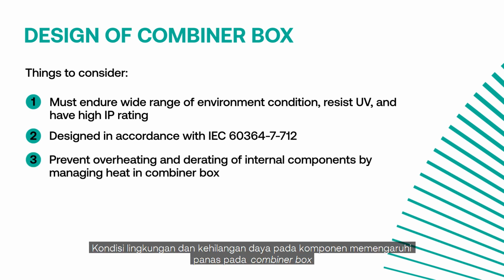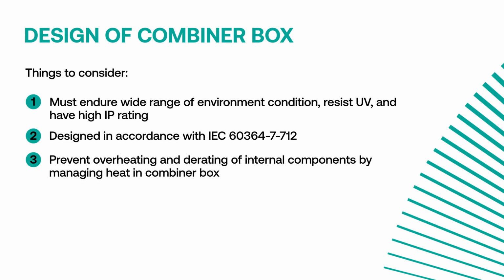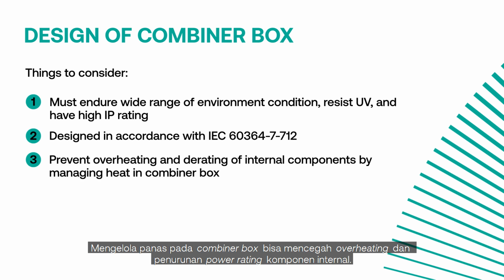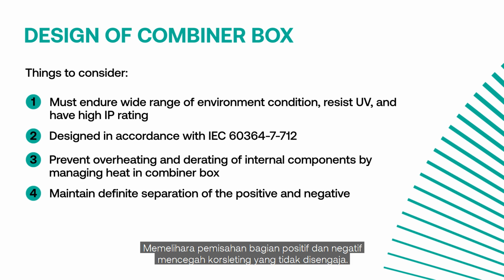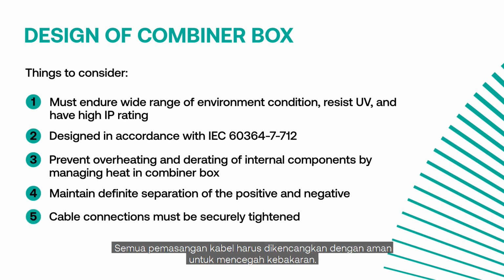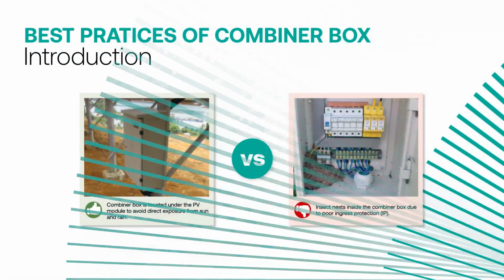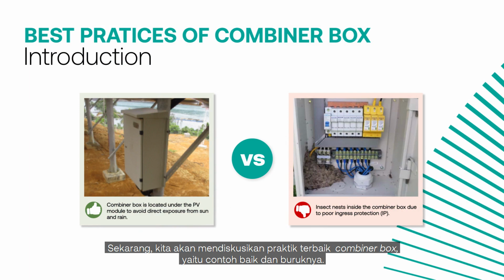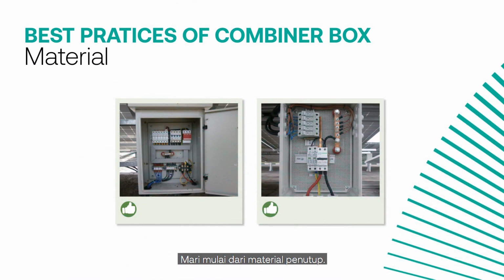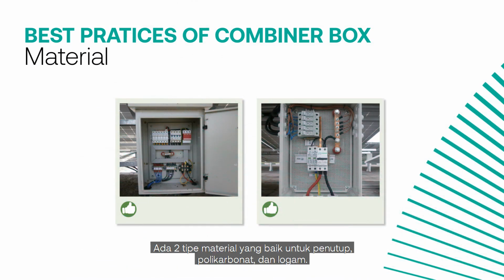Solar photovoltaic power supply systems. Ambient conditions and power losses of the components affect the heat in the combiner box. Managing the heat in the combiner box can prevent overheating and derating of the internal components. Maintaining definite separation of the positive and negative sides prevents accidental short circuit. All cable connections must be securely tightened to prevent fire hazards. Now, we are going to discuss best practices of combiner boxes, that is, the good and bad examples. Let's start with the enclosure materials.